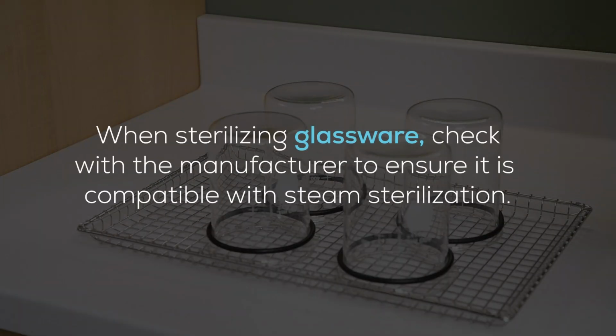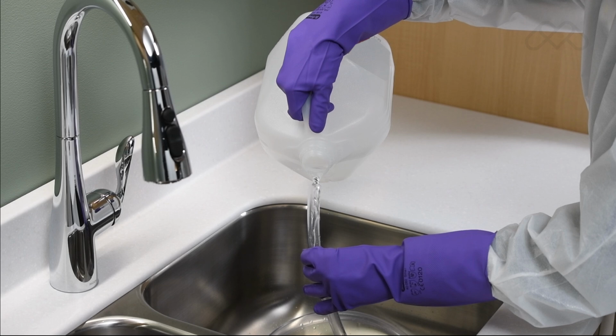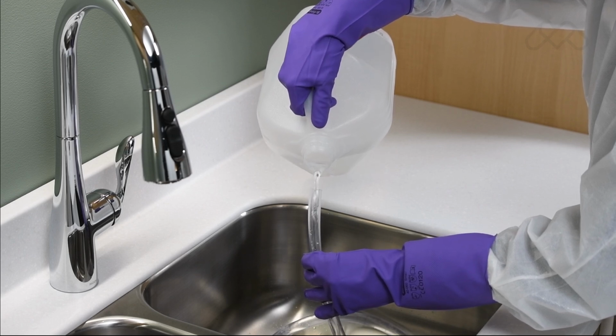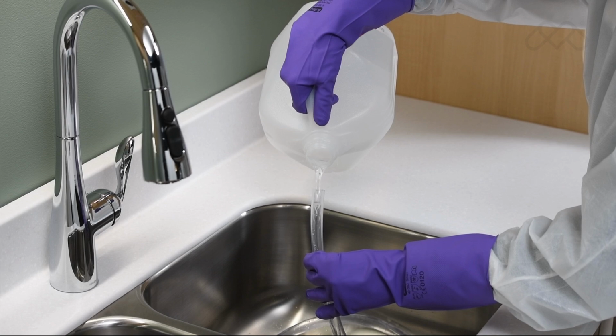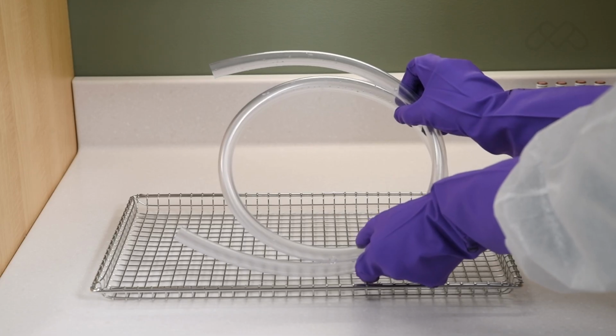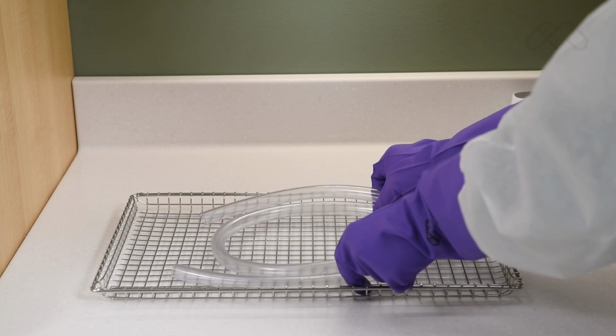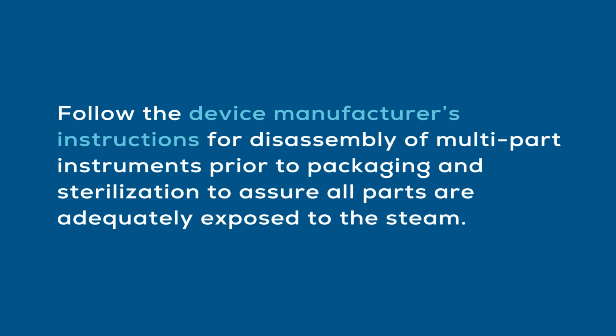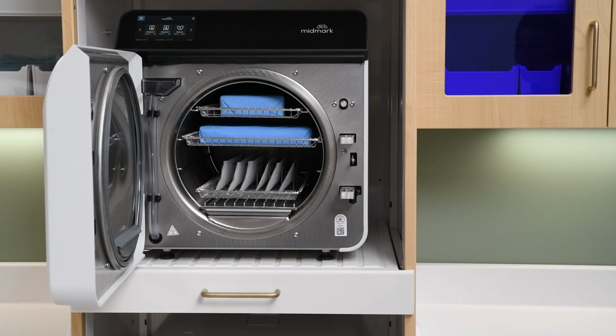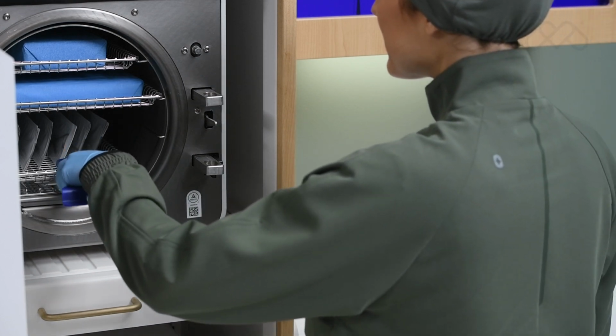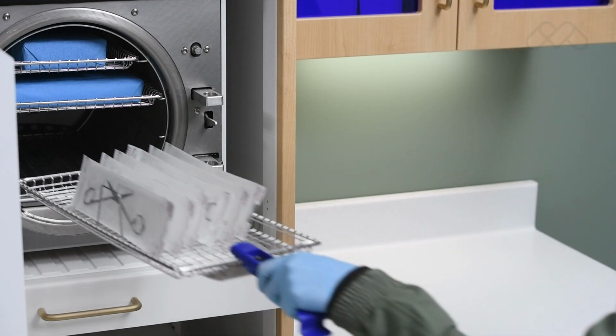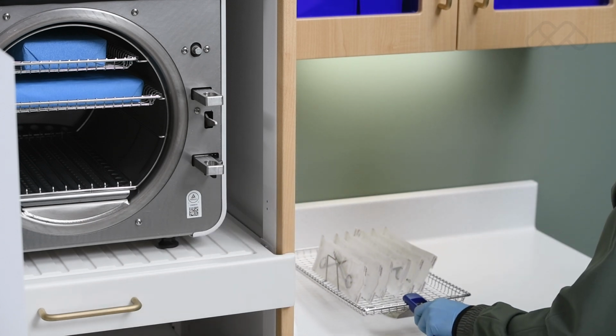When sterilizing glassware, check with the manufacturer to ensure it is compatible with steam sterilization. Rinse tubing with distilled water or water that meets the referenced water purity specifications and do not dry prior to sterilizing. Arrange tubing on the tray so there are no sharp bends and the tubing ends are open and unobstructed. Follow the device manufacturer's instructions for disassembly of multi-part instruments prior to packaging and sterilization to assure all parts are adequately exposed to the steam. If items are being sterilized and stored for later use, they must be packaged and completely dry when removed from the sterilizer chamber to avoid potential recontamination.